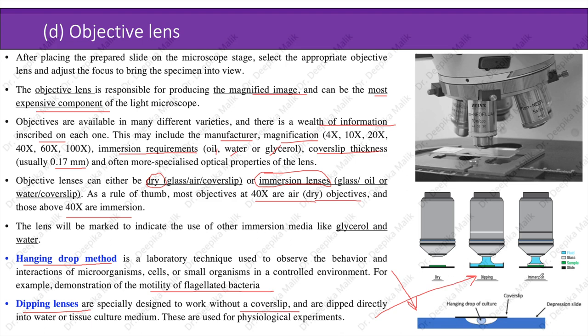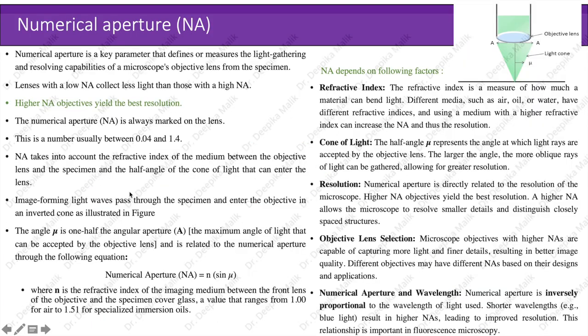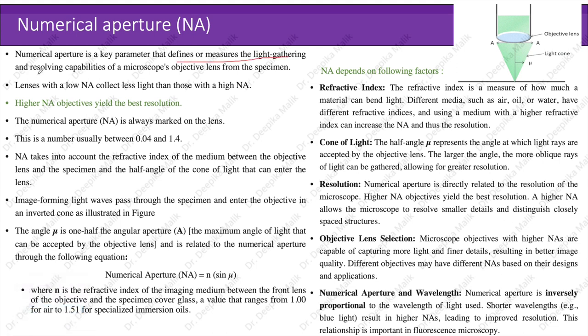Numerical aperture is a key parameter that defines the light-gathering and resolving capabilities of a microscope's objective lens. Lenses with low numerical aperture collect less light than those with high numerical aperture; higher numerical aperture objectives yield the best resolution. The numerical aperture is always marked on the lens and is usually a number between 0.04 and 1.4. It takes into account the refractive index of the medium between the objective lens and the specimen, and the half-angle of the cone of light that can enter the lens.